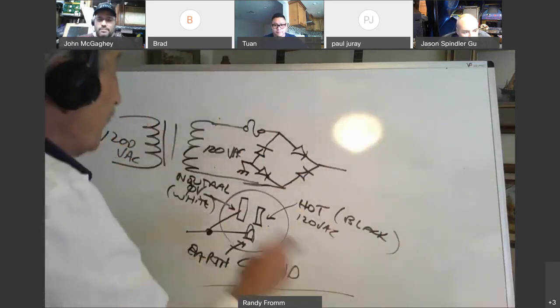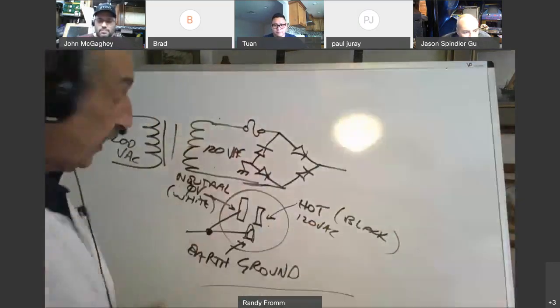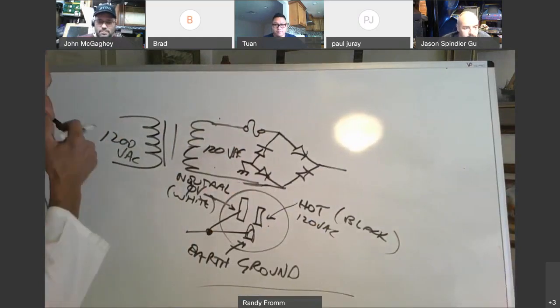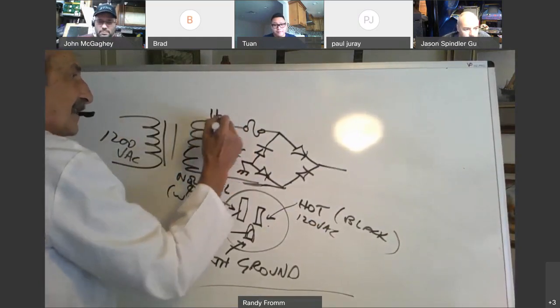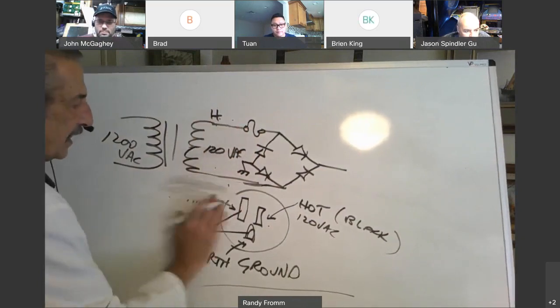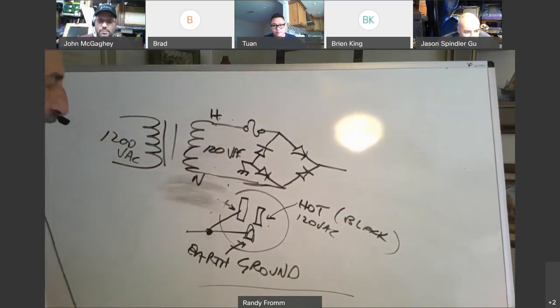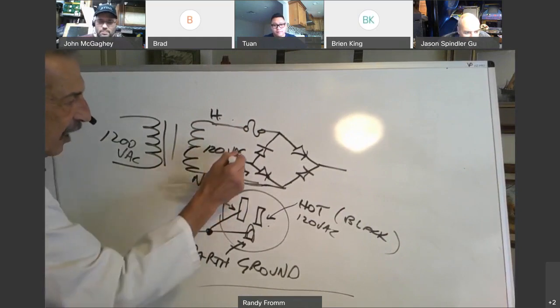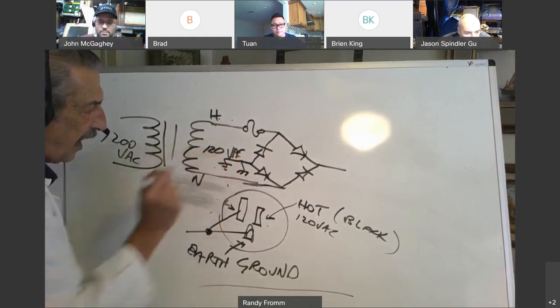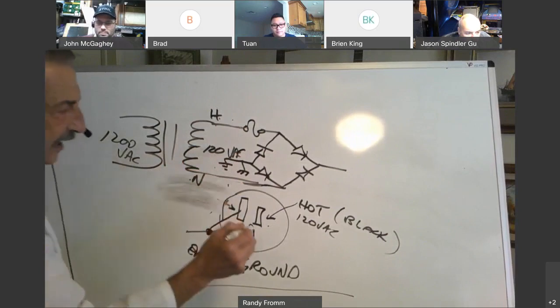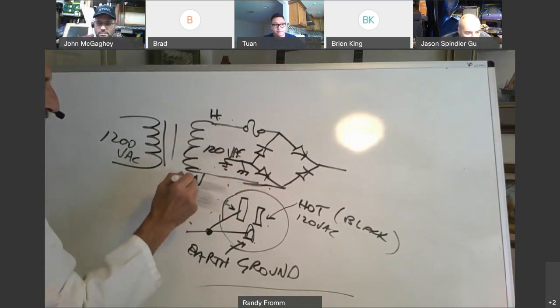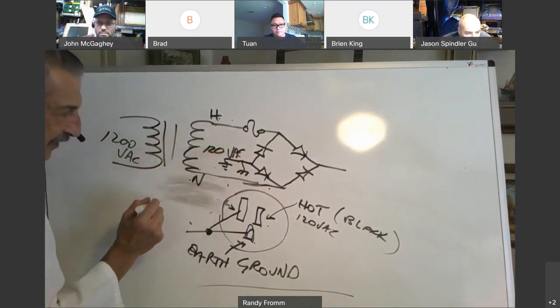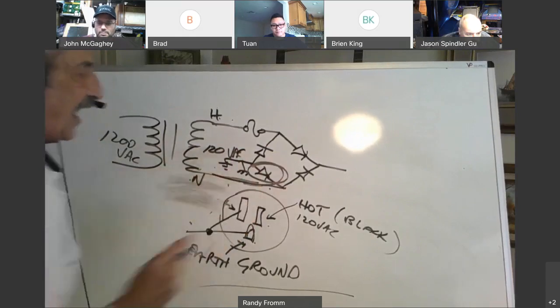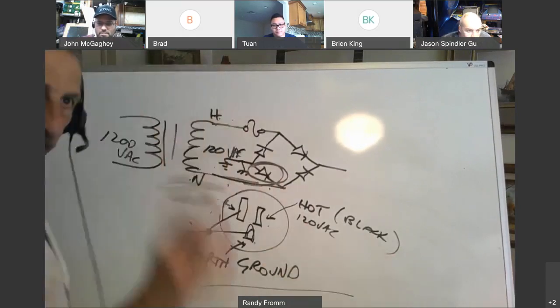The earth ground goes to the outside so you don't get a shock, while the neutral goes to the inside to all the electronics. But these two are connected together. So imagine this is the hot side of the AC power, and this is the neutral side. If we hook this up to earth ground, since neutral and ground are connected together, connecting an earth ground here shorts out that diode — it's just a dead short. This may have happened to you.